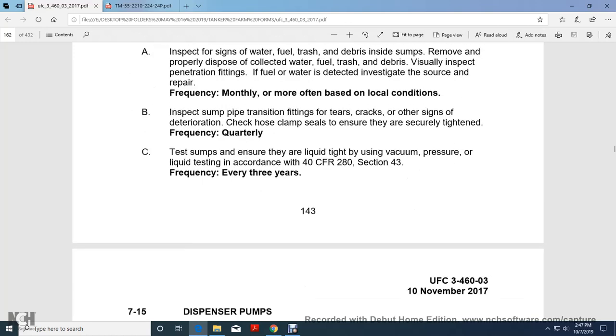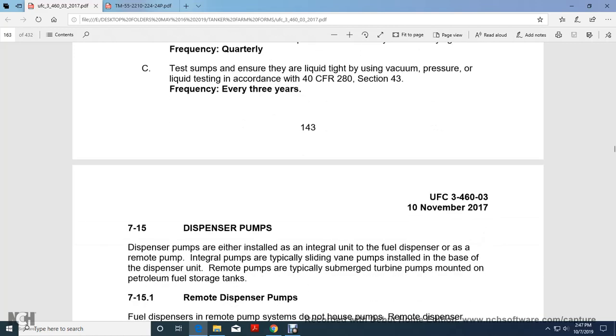Inspect the sump, pipe, and piping transition for tears, cracks, and signs of deterioration. Check the hose clamp seals to ensure they are securely tight, quarterly. Test transition sumps to ensure they are liquid tight using vacuum, pressure, or liquid testing according to Title 40 CFR 280, Section 43, every 3 years.